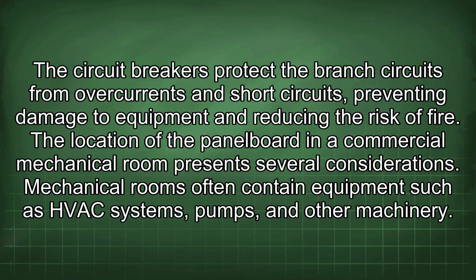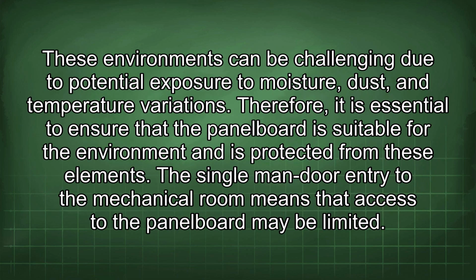risk of fire. The location of the panel board in a commercial mechanical room presents several considerations. Mechanical rooms often contain equipment such as HVAC systems, pumps, and other machinery. These environments can be challenging due to potential exposure to moisture, dust, and temperature variations. Therefore, it is essential to ensure that the panel board is suitable for the environment and is protected from these elements. The single-man door entry to the mechanical room means that access to the panel board may be limited.